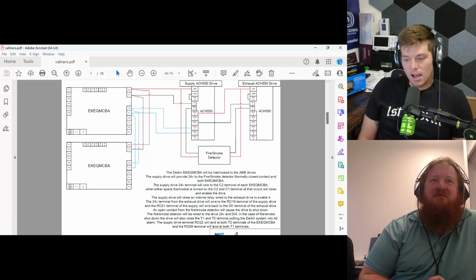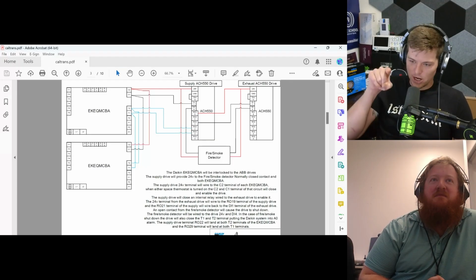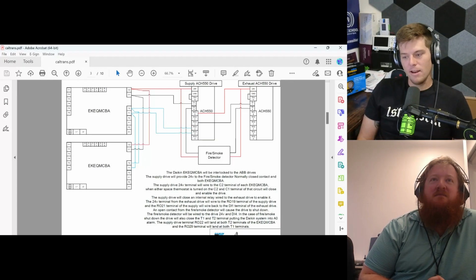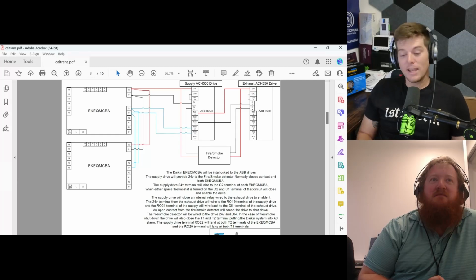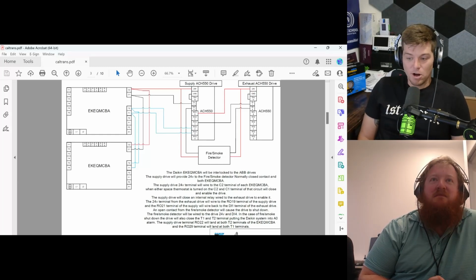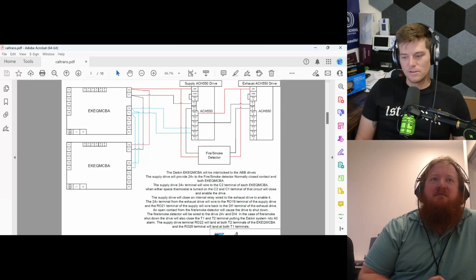The drive locks out, and rightfully so because it's not auto reset, and you have to go jam the button on the drive on the roof in the rain. Those are the things that happen. But yes, like you're saying, life safety - should it be auto reset? No, it should reset when the contact has been cleared and you have the demand signal again.